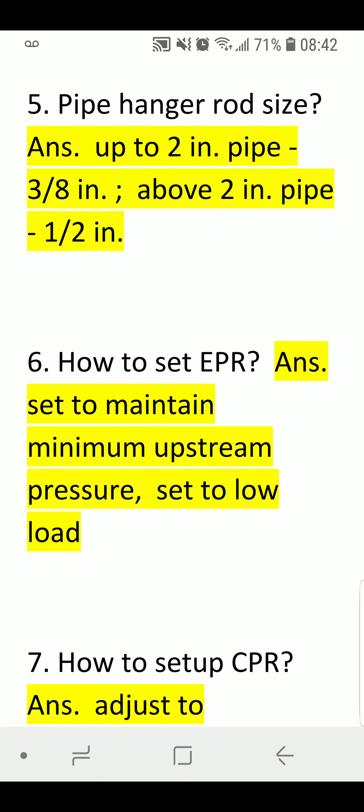Pipe Hanger Rod Size. Answer: Up to two-inch pipe — three-eighths inch rod. Above two-inch pipe — one-half inch rod.